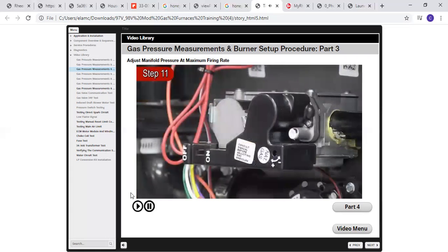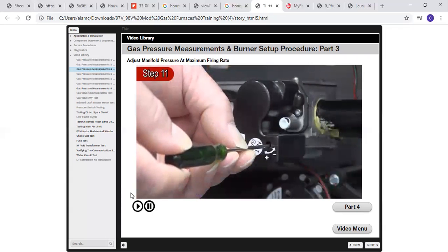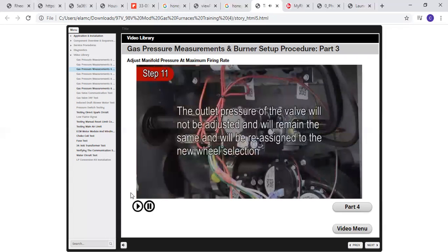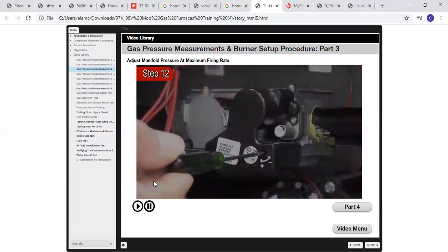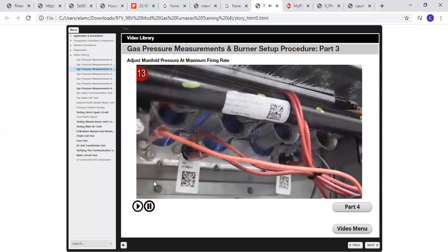If power to the furnace, and therefore the gas valve, has been interrupted and the adjustment wheel turns while the power is off, the outlet pressure of the valve will not be adjusted and will remain the same and will be reassigned to the wheel selection. Step 12. Repeat steps 10 and 11 if necessary.